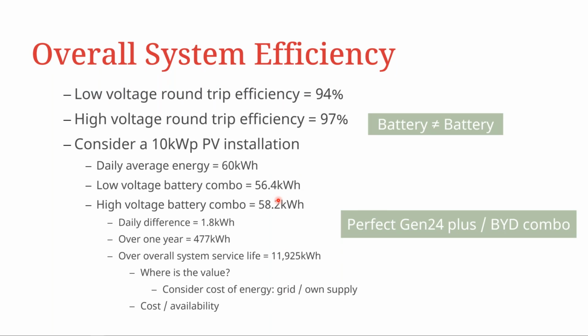When mentioning the overall system efficiency, low voltage round trip efficiency is about 94%, whereas high voltage round trip efficiency is 97%. If you're considering a 10 kilowatt peak PV installation, your daily energy is 60 kilowatt hours. This will give you a low voltage battery combo of 56.4 kilowatt hours available, whereas the high voltage battery combo gives you 58.2 kilowatt hours available. So this gives you a daily difference of 1.8 kilowatt hours.